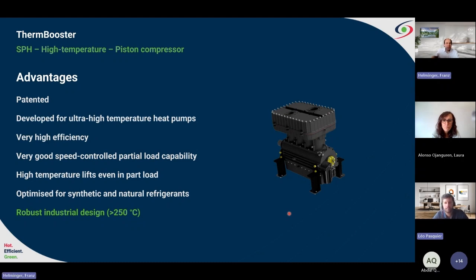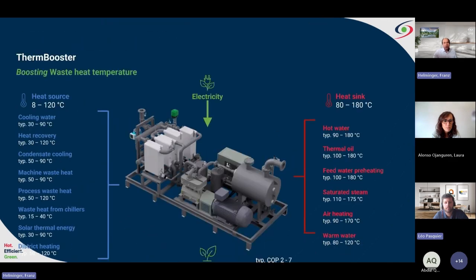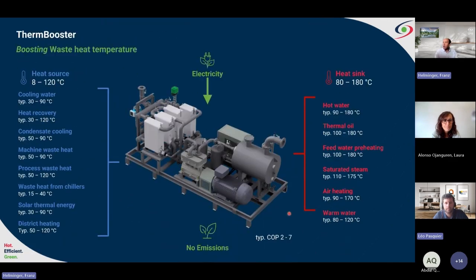The next slide gives a little bit the same information that Laura already gave. That's the principle of such a vapor compression heat pump. It addresses the temperatures our machines can address, but I will not go through all these details. In the center of the slide, you can see a basic design of our heat pump. On the left-hand side, we have the evaporators, which are basically plate heat exchangers and some internal heat exchangers. We have our core technology, the compressor, connected to an electrical motor. And here we have a steam generator.